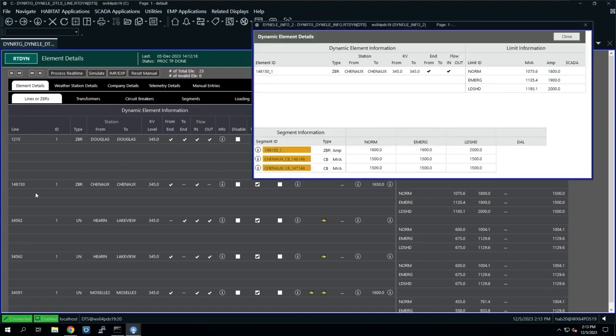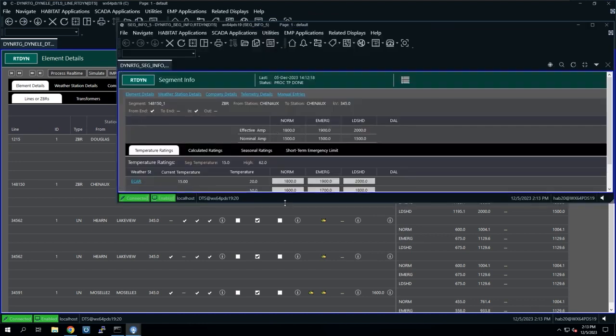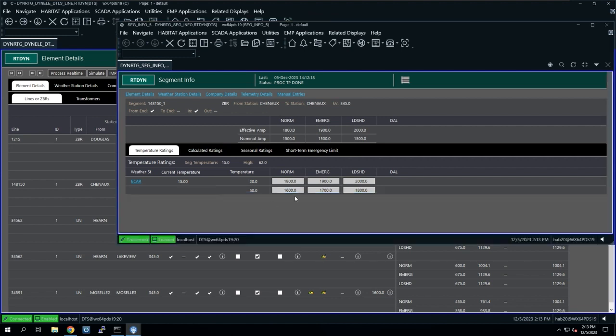So as an example, this line, 148150, we currently are using an ambient adjusted rating table on this line. So it's a very small table. It just has a rating of 20 degrees ambient and 50 degrees ambient. The current temperature is 15. It's going to use the next most conservative rating set. So it's going to pull this first rating set out of this table for normal, emergency, and load shed. So you can see here what the effective rating is at 1800, 1900, and 2000.